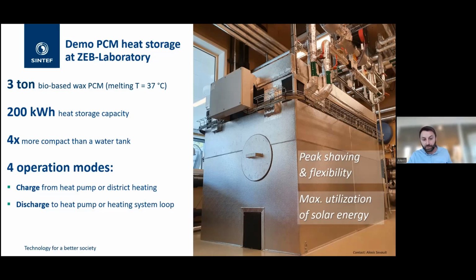Remember, it was 37 degrees, the melting temperature of the PCM. That means we work mostly between 35 and 40 degrees with this heating system. At 40 degrees we can melt the PCM and charge the storage, and when we discharge it we get hot water at 35 degrees. But the way we run this low temperature heating system in the building, it's enough to keep it warm. That's what's interesting - it was a kind of innovation developed in this building to run on low temperature heating.